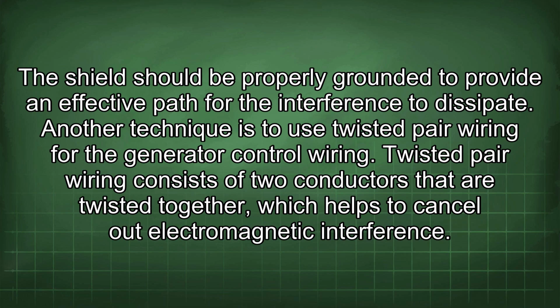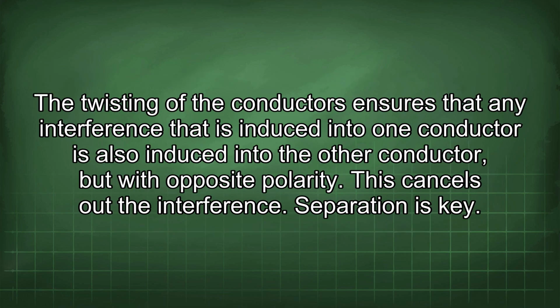Another technique is to use twisted pair wiring for the generator control wiring. Twisted pair wiring consists of two conductors that are twisted together, which helps to cancel out electromagnetic interference. The twisting of the conductors ensures that any interference that is induced into one conductor is also induced into the other conductor, but with opposite polarity. This cancels out the interference.